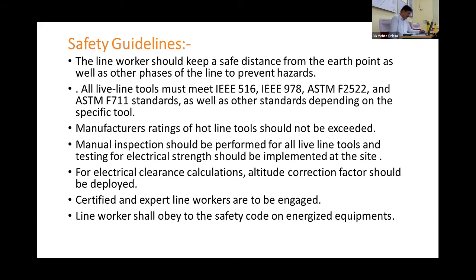There's also PID, puncture insulation detection, being carried out by hotline people in many states. Bare hand methods and fast jumpering work on the hot stick, replacement of the jumper, and thermography of the CVT, CT, etc. for any insulated wave trap is done with live line meters. This avoids outage of the network and gives consistency and reliability.